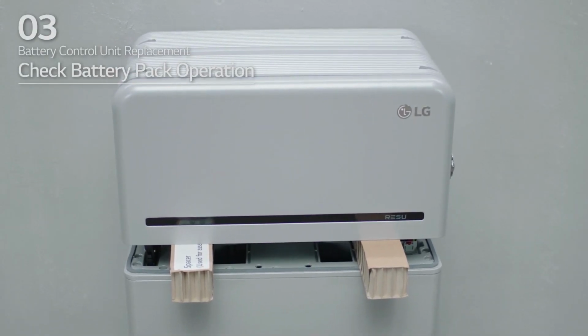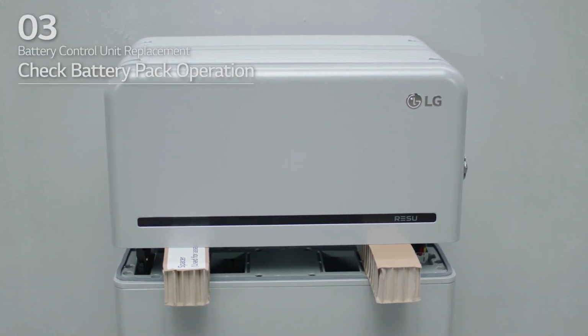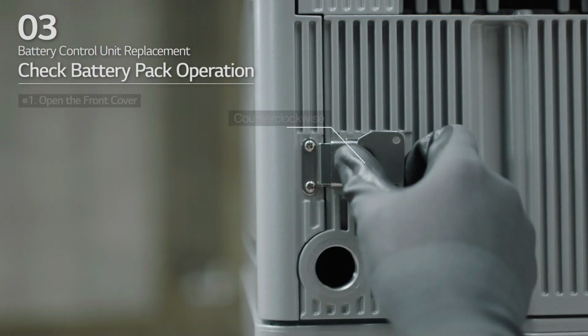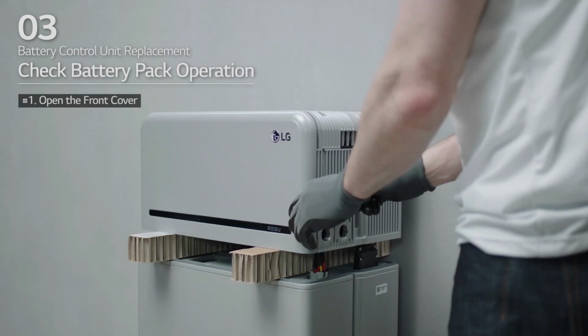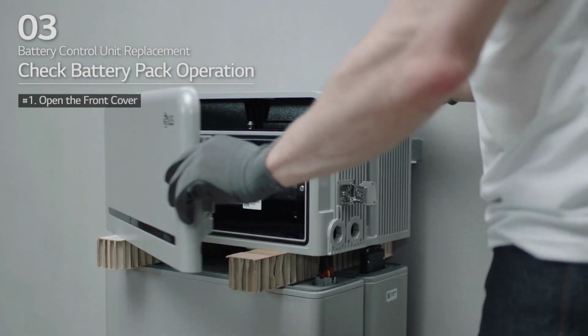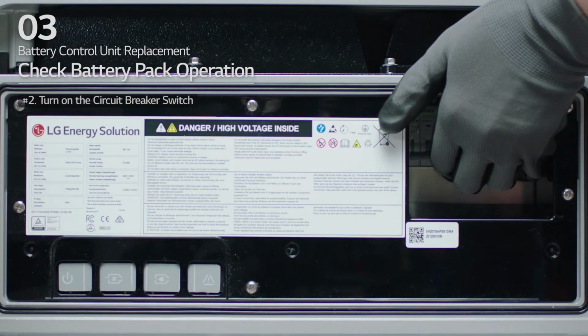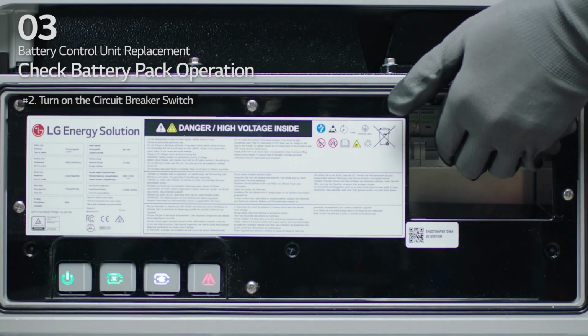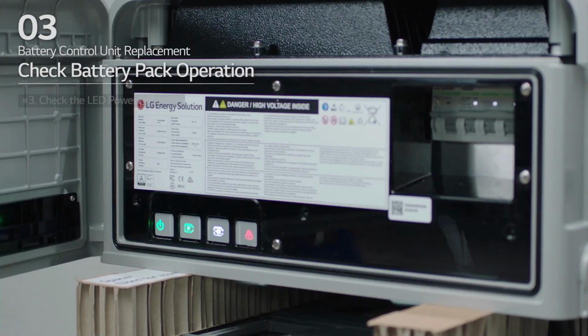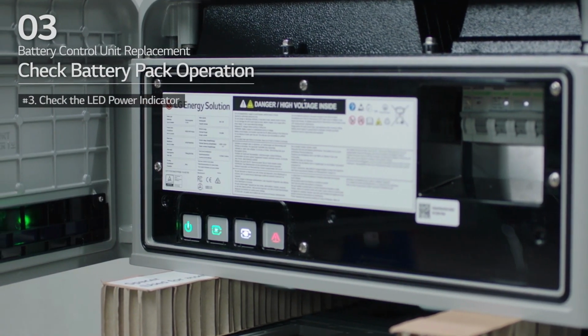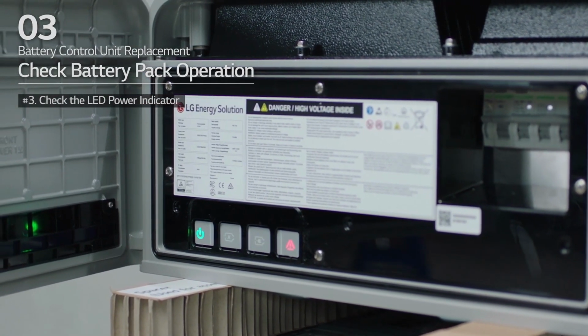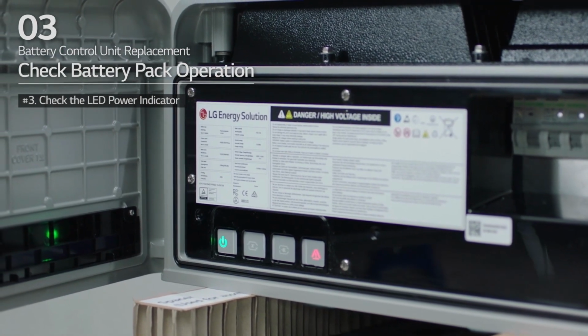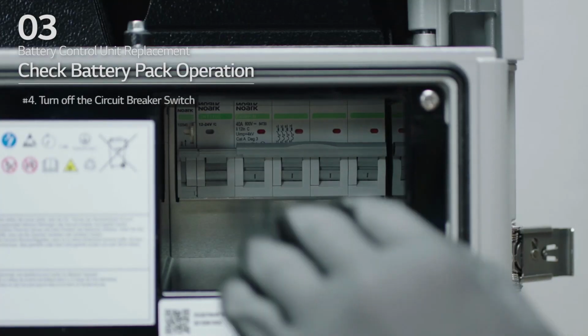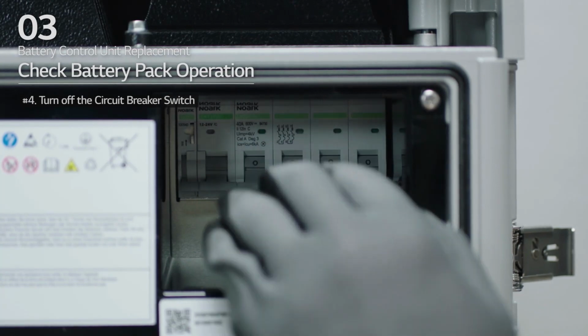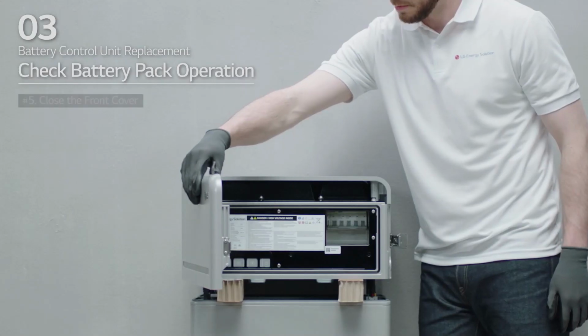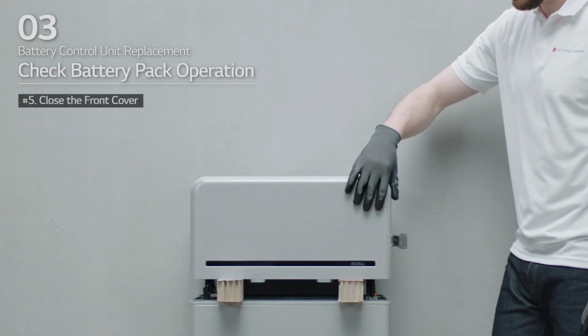After that, check that the battery pack is operating properly. First, hold and turn the handle counterclockwise and open the front cover. Then, turn on the circuit breaker switch. Check that the LED power indicator is turned on and that 60 seconds later, the LED fault indicator is blinking. If there are no problems, turn off the circuit breaker switch and close the front cover.